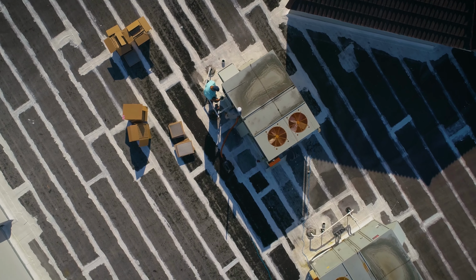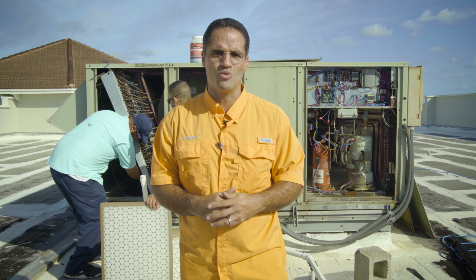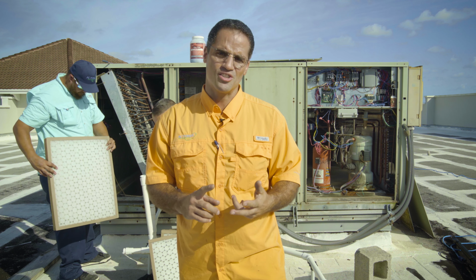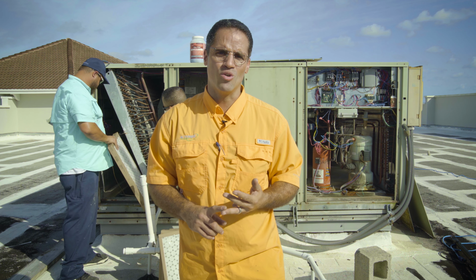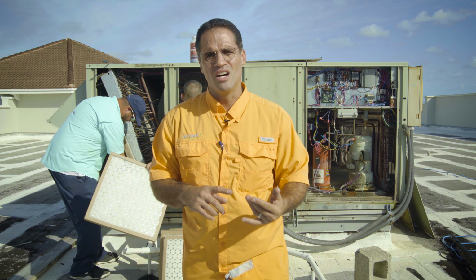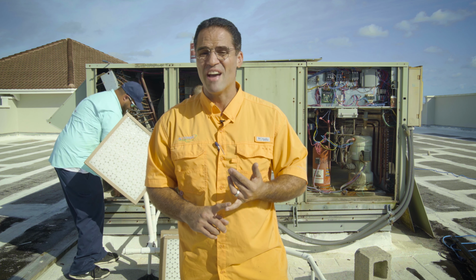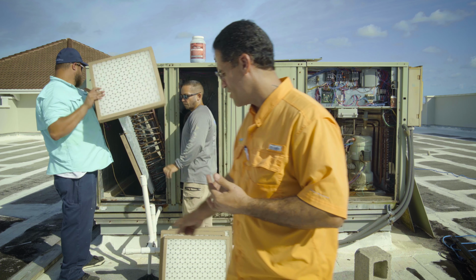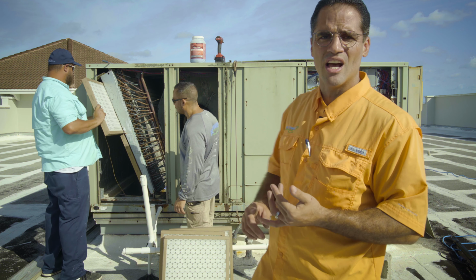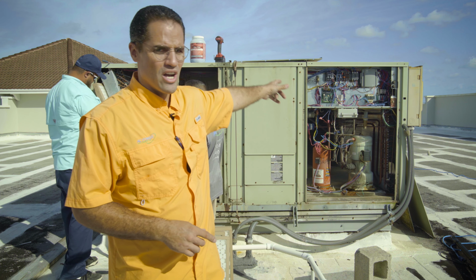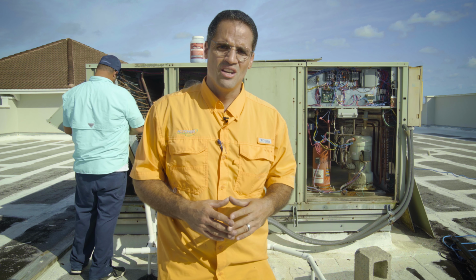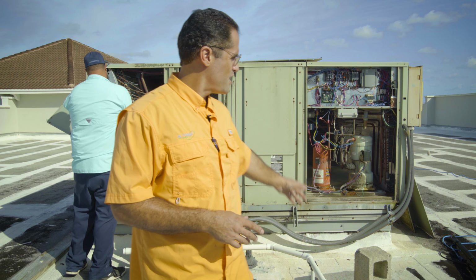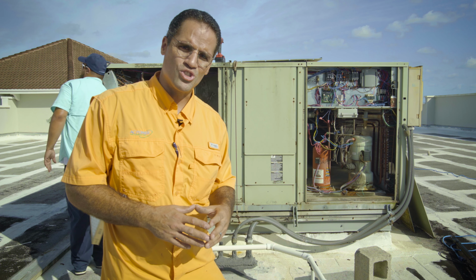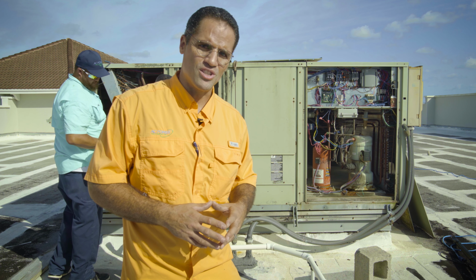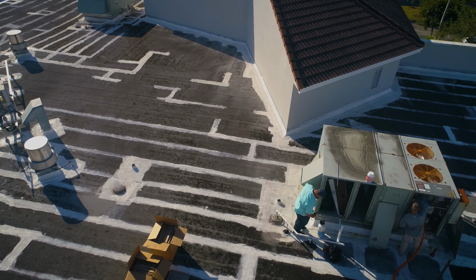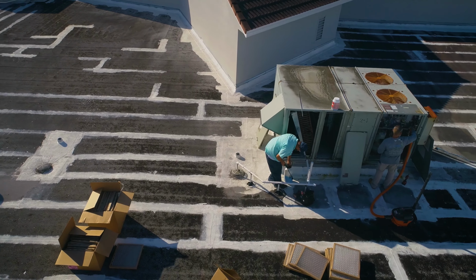Just an overview of what we did today in our preventative maintenance: change filters, sanitize coils, check or change the belts if required, gel tablets in the drain pan, vacuum out the piping here on the condensate drain line, check electrical as well for any type of discoloration or anything loose, and then check for any refrigerant leaks, oil stains, and also take pressures if needed. Pretty much that's what sums up our preventative maintenance for a commercial package unit.